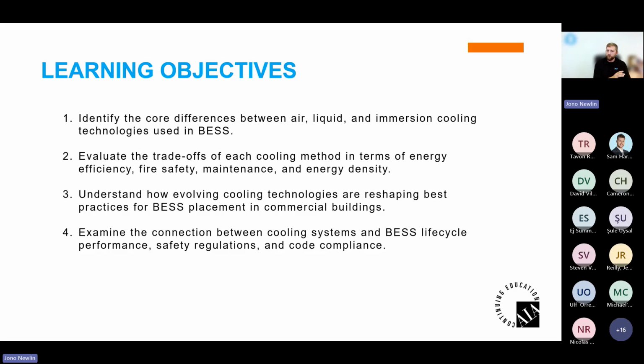Is this going to be out in the middle of nowhere where we want the cheapest product? Okay, air-cooled is probably going to be lower CapEx up front. We want liquid cooling because it's the standard in the market, we can get that, but we need to know the risks of how it could cause, or doesn't prevent, thermal runaway. Or where is this location? Next to schools, critical infrastructure, personnel, or residential units? We want to look at maybe immersion cooling as a better fit where we can get over AHJ approval and community pushback. We have that at our fingertips.